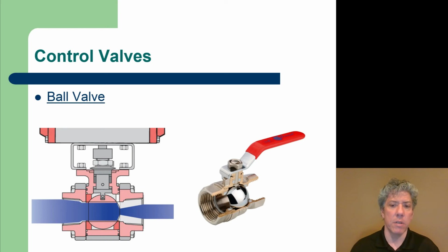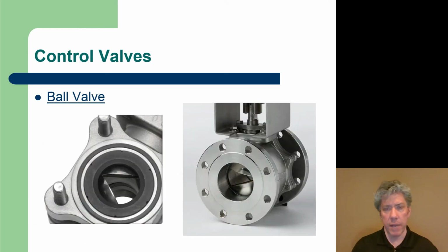One of the disadvantages of these, you might think that you could partially turn it on. It's very difficult with a ball valve to get an exact flow rate through it, because as soon as you just start opening, even 5% or so, you get pretty much full flow through the ball valve. Now, to overcome that, other valves have been developed where rather than having just a straight hole going through them, they have a variable opening. Imagine the sphere turning and exposing a very small area and then opening up to larger and larger area to allow more and more flow. So these are much better proportioning valves rather than just on, off, as the typical ball valve with a hole straight through it is good for.